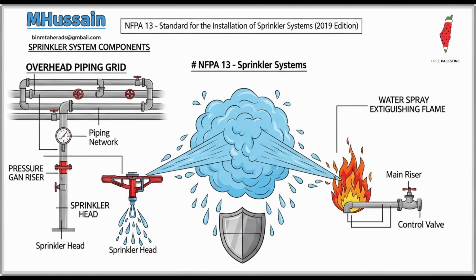What about small concealed spaces, say, in light hazard areas like offices? Right. For light or ordinary hazard occupancies, sprinklers can be omitted entirely in small concealed spaces. This applies specifically where you have non-combustible or limited combustible ceilings attached directly to solid wood joists, creating these little enclosed spaces that are 160 cubic feet, that's 4.5 cubic meters, or less in volume. The logic here is basically that a fire can't gain enough thermal momentum or have enough fuel load in such a tiny compartmentalized space to pose a real structural threat before the main room system activates.